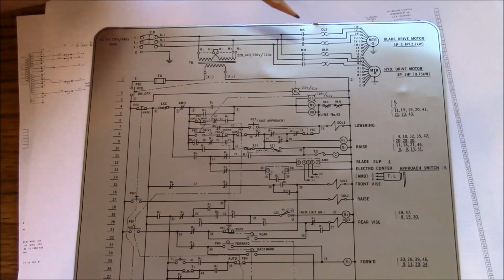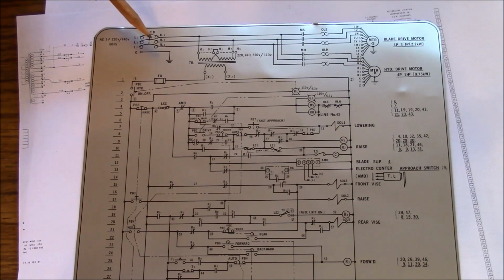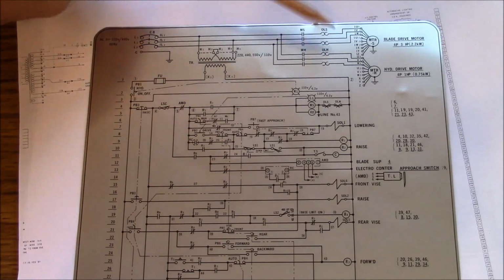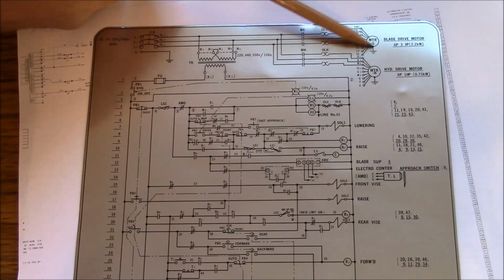There are no fuses here, they must be protected by the main circuit breaker. So the circuit breaker protects the wire, and the heaters protect the motor.